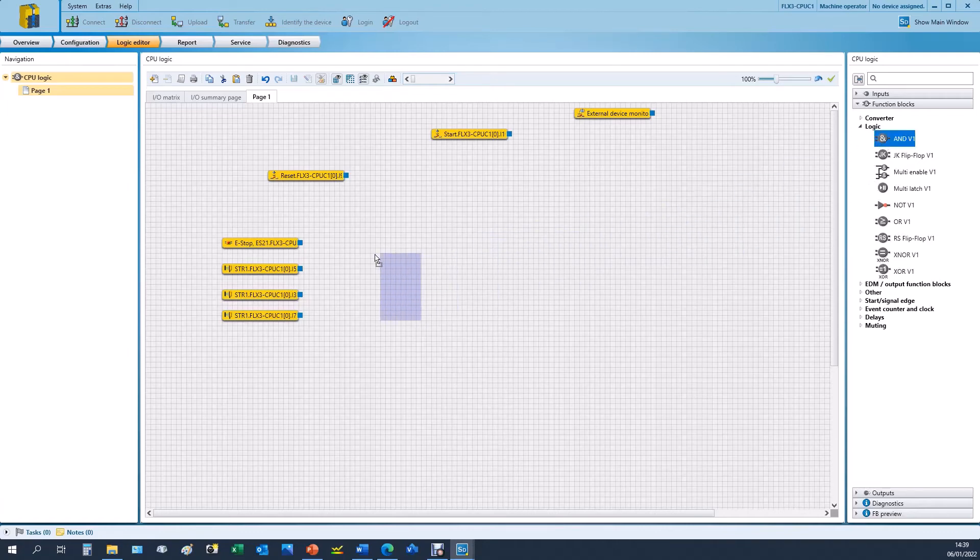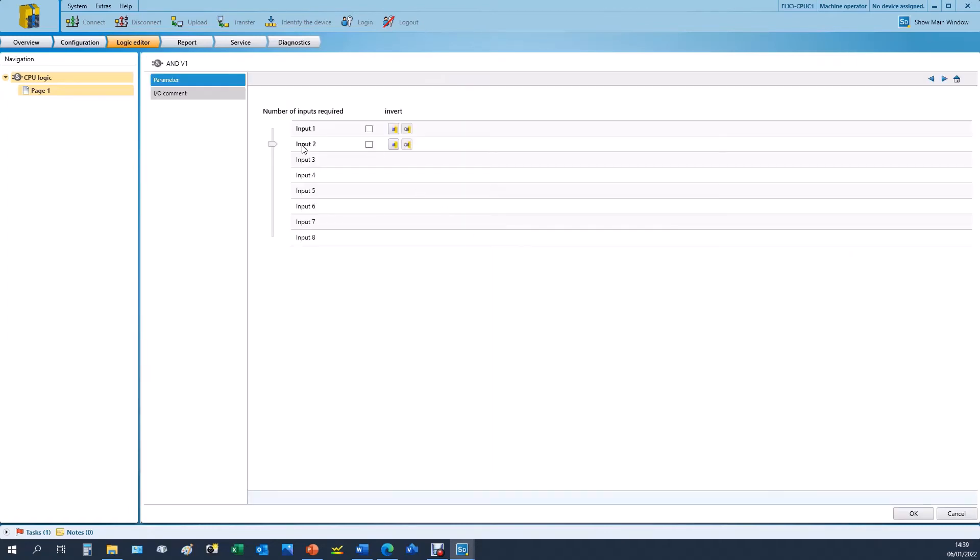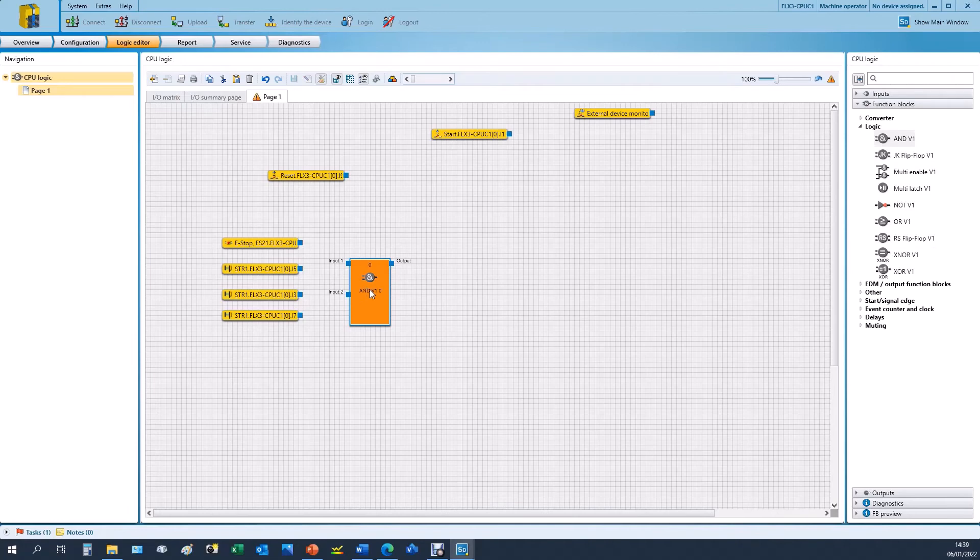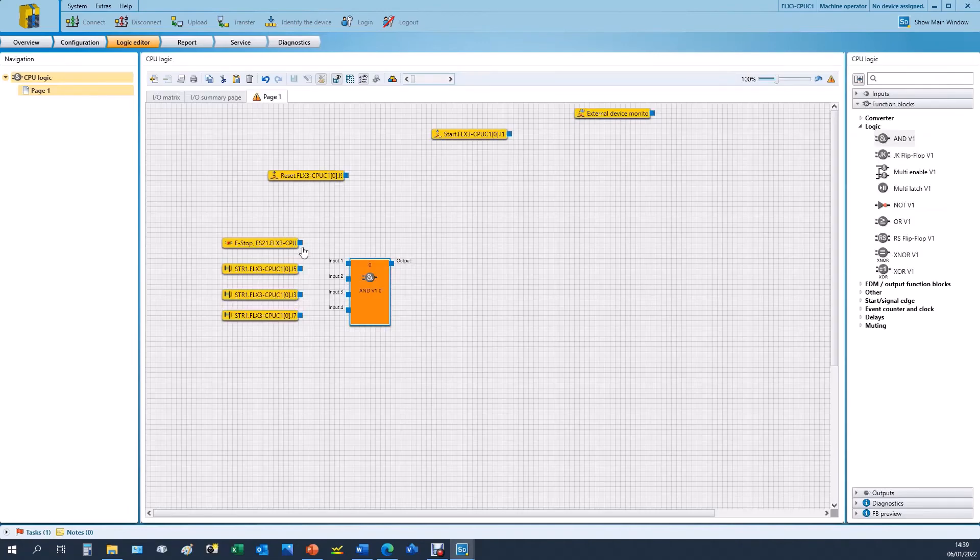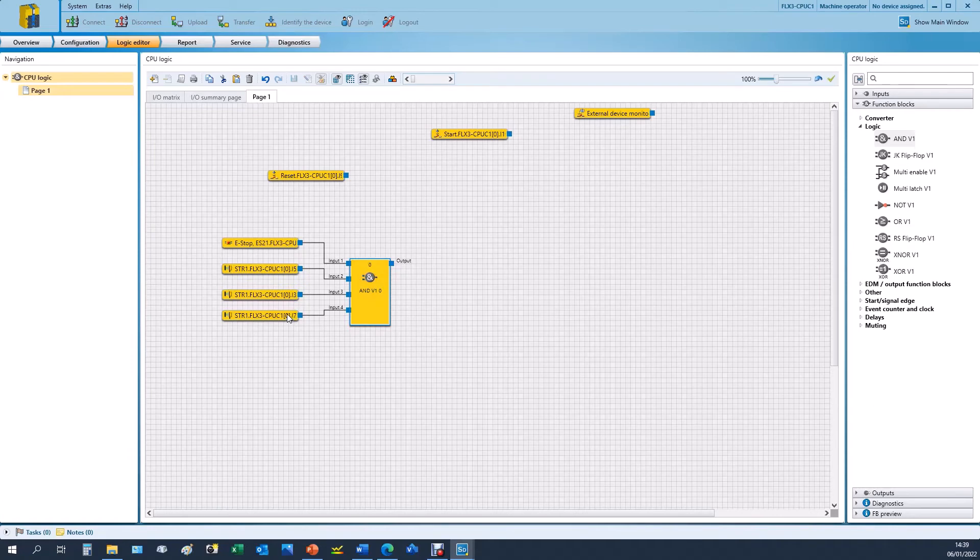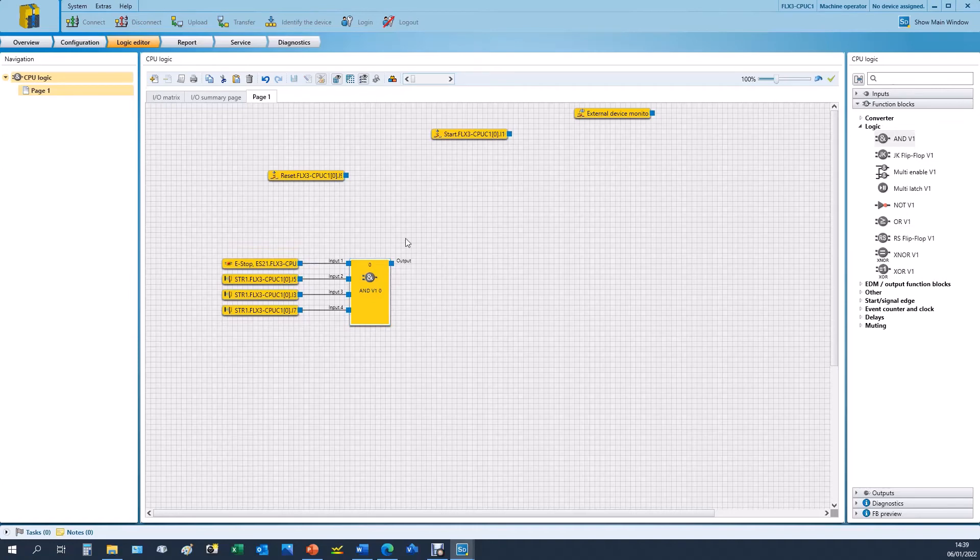So we want to AND or series up all of these four inputs together. If you double-click the function block you can change the options. I'm going to change that AND block to four inputs and then you simply drag and drop the lines together and the function block turns yellow when you've successfully wired everything together to say that you've wired it up correctly. So that's an AND function, so all of these have to be high in order for the output to go healthy.